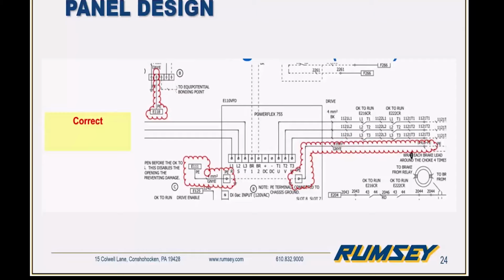One way to ensure that proper grounding methods are followed is to make sure that our wiring diagrams properly illustrate the correct grounding methods. So here's an example of a wiring diagram. We can see here the motor ground and shield going back to the drive, and a separate ground that goes over to our panel. Again, it's just good to enforce that we do the proper grounding.